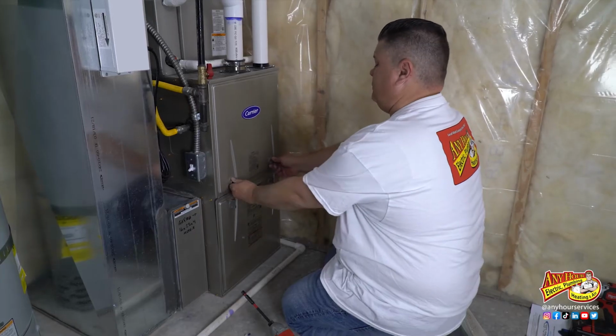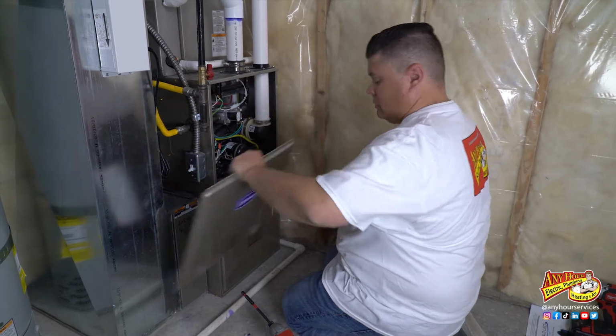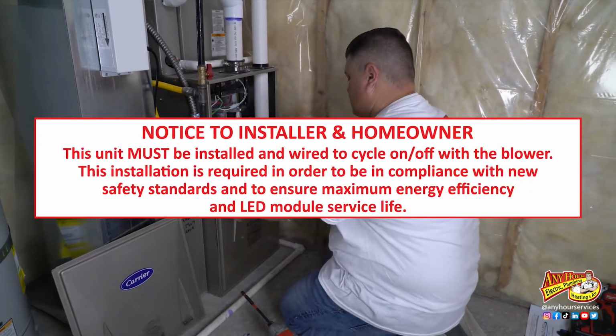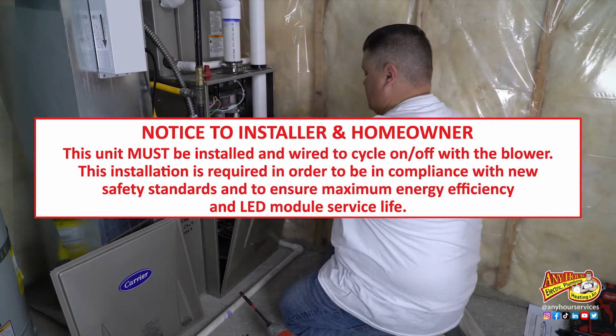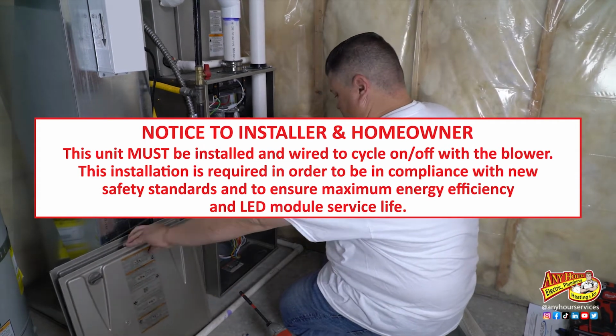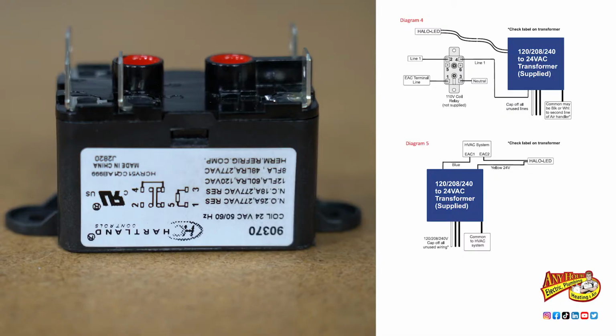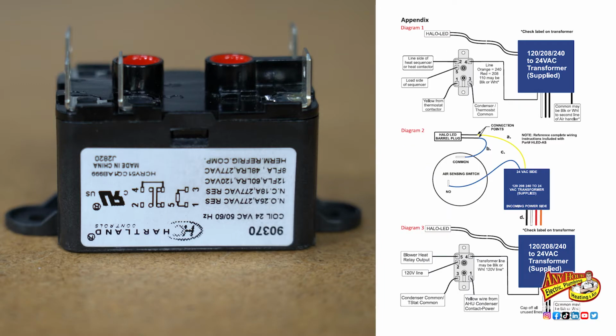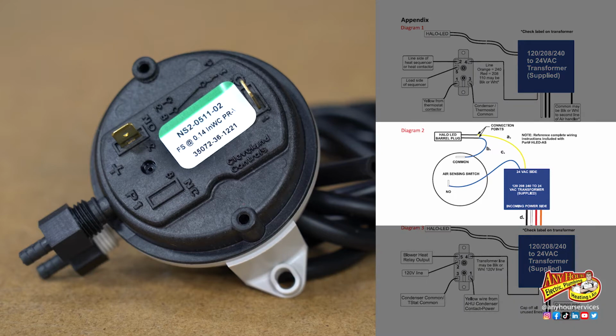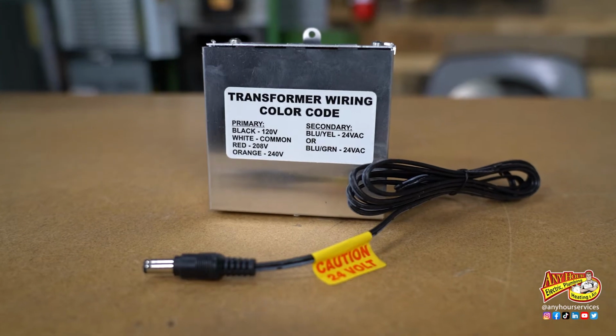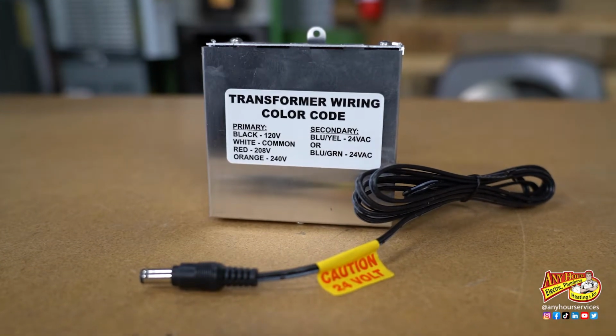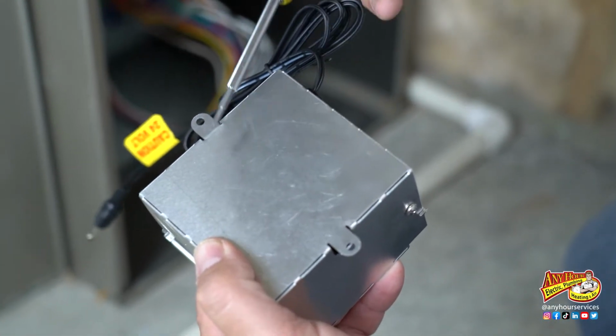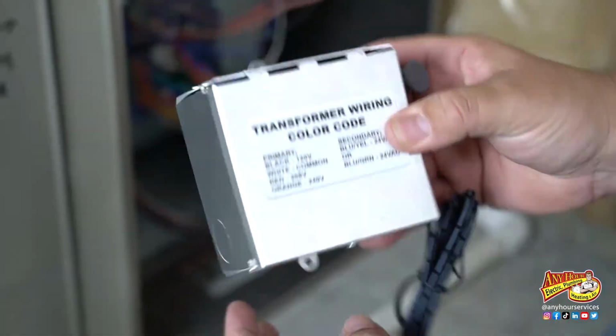Now we can move on to the electrical connections. Remember, the Halo LED must be installed and wired to cycle on and off with the blower. There are different wiring configurations you can use with the relay depending on your specific installation, but RGF recommends using the air switch since it's the simplest and most universal install. Be sure to use the supplied 24-volt transformer that comes with the unit. It comes in a metal box in case you have to install it outside of the furnace enclosure.